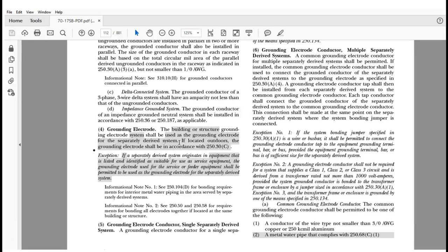Okay? Not necessarily the electrode. For example, water piping within 5 feet of the point of entry is part of the electrode. But now it's saying that as it extends through the building, it can actually extend that connection, and that's covered in 250.68(C)(1) and (2). Okay? So nothing really changed there. They do extend that. But at this point, there isn't any hierarchy. Basically, if I have a separately derived system in that building or that structure, whatever grounding electrode system is in that building shall be used. Okay? So that was a significant change when you're dealing with that.